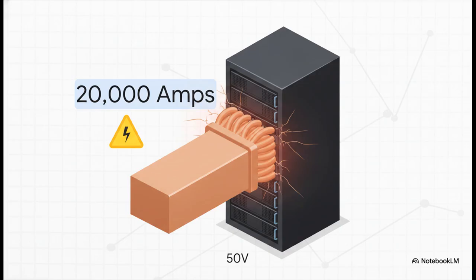If you try to distribute just 1 megawatt of power using a traditional 50-volt architecture, it requires a staggering 20,000 amps of current. Trying to push that much current through traditional bus bars would require copper that is unimaginably heavy, expensive, and dense. Actually, scratch that—it literally wouldn't even fit inside the rack.